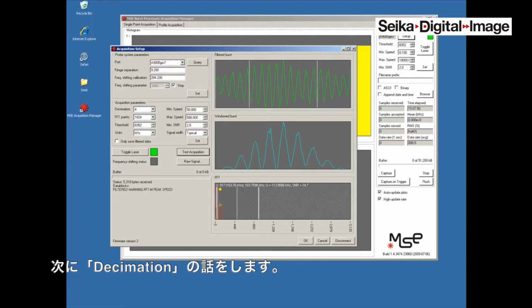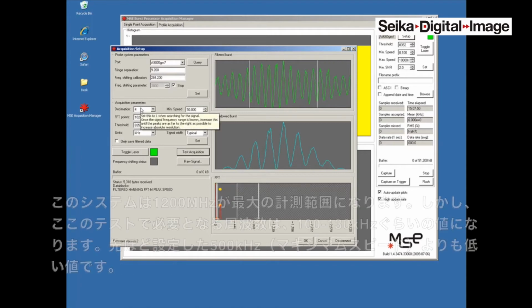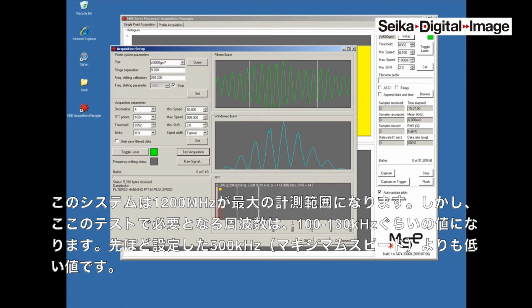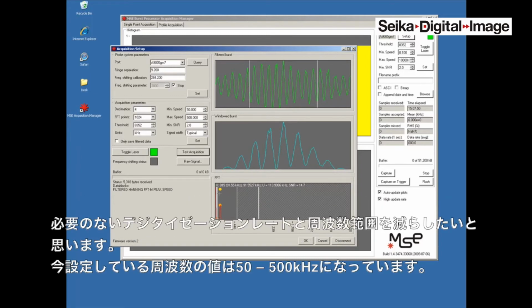Now, if we haven't talked about decimation: the maximum digitization rate of this system is 12.5 megahertz. But since our frequency is at 113 or 100 kilohertz thereabouts, or less than 500 kilohertz, you would like to reduce the digitization rate to match the frequency range that you work with. The frequency range that we work with is 50 to 500, let's say, kilohertz.